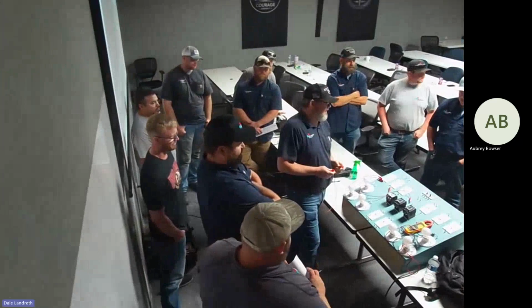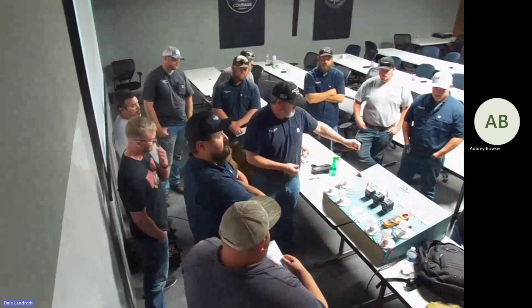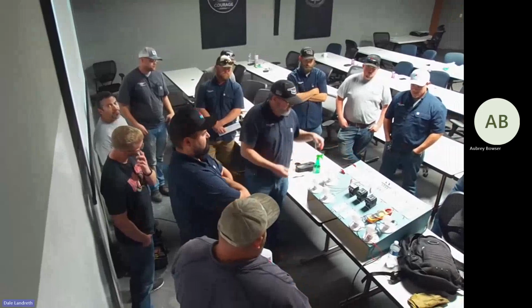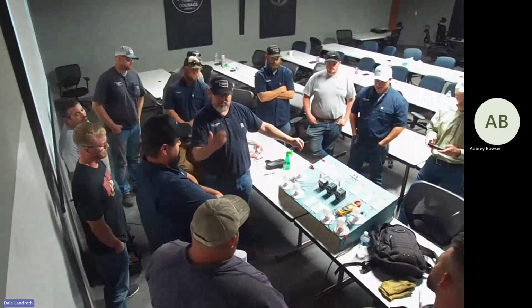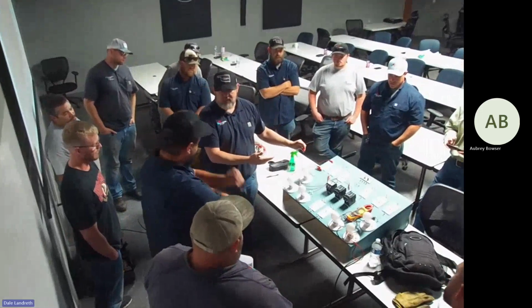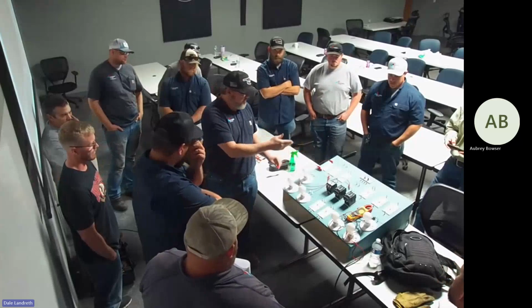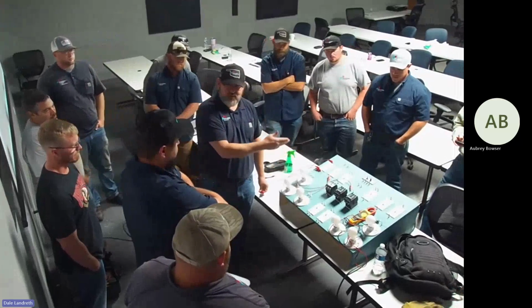Got it. Okay, so we're gonna go off of Y. That's got to turn the contactor on, but low pressure and high pressure need to be able to turn that off. So we need to wire those in parallel to the compressor contactor, or series.